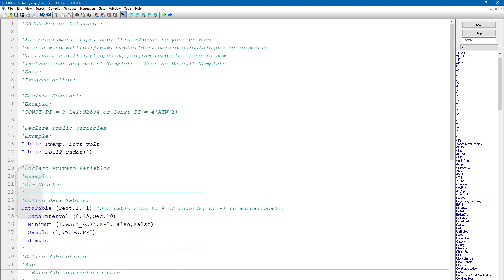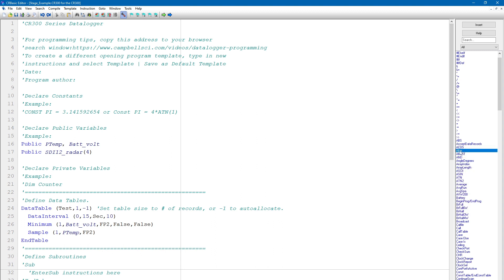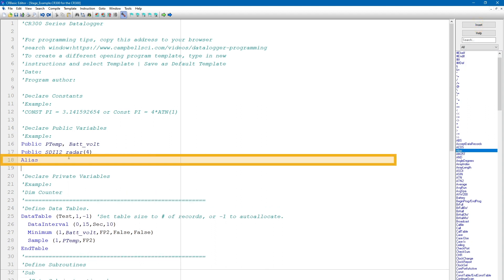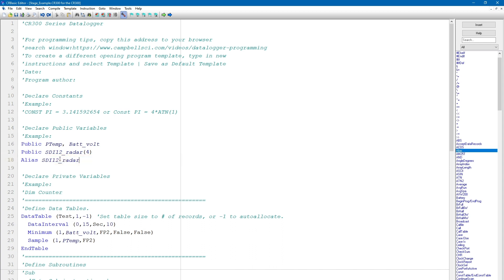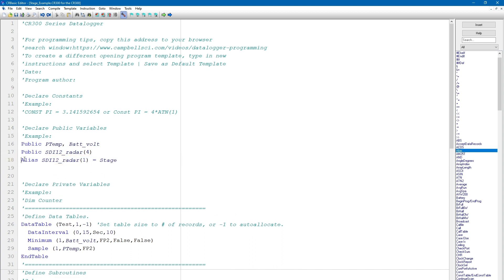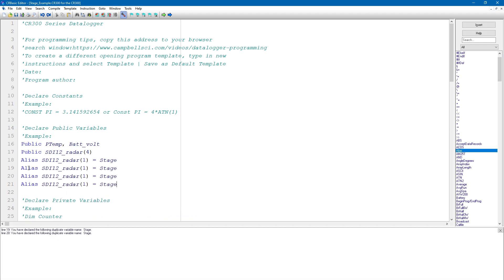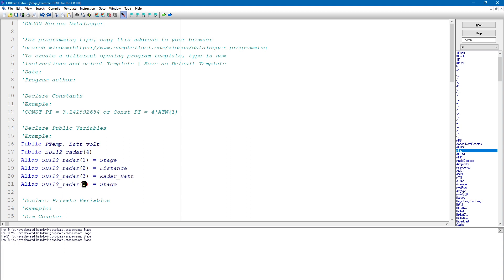I start by putting my cursor where I want to insert the alias, and then I go to the instruction toolbar, click on alias, and then click insert at the top of the instruction list. First, I type SDI 12 Radar 1 equals stage. Then I copy and paste this 3 times and modify each line so I have alias SDI 12 Radar 2 equals distance, alias SDI 12 Radar 3 equals Radar bat, and alias SDI 12 Radar 4 equals Radar error code.